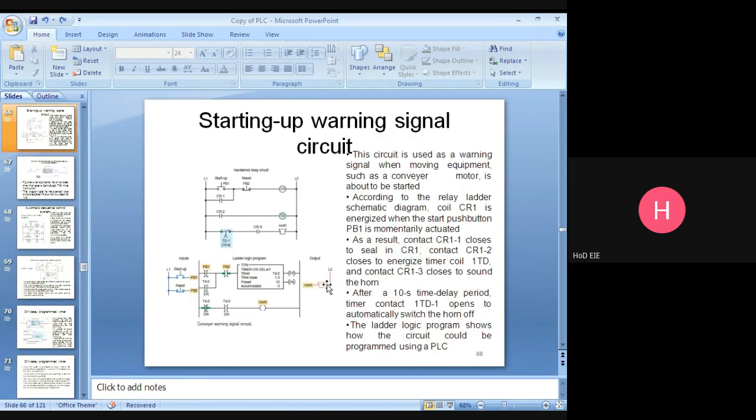So this one is the PLC instruction. This one is your relay logic. This one is your PLC logic. Instead of this push button, I'm using contacts. Same, this one is on; I'm using a coil this way. Here I'm using the on delay instruction. Once PB1 is pressed, the enable bit will be energized. Once the enable bit is energized, the same address is given here. So this contact is closed, so this instruction will keep energized.